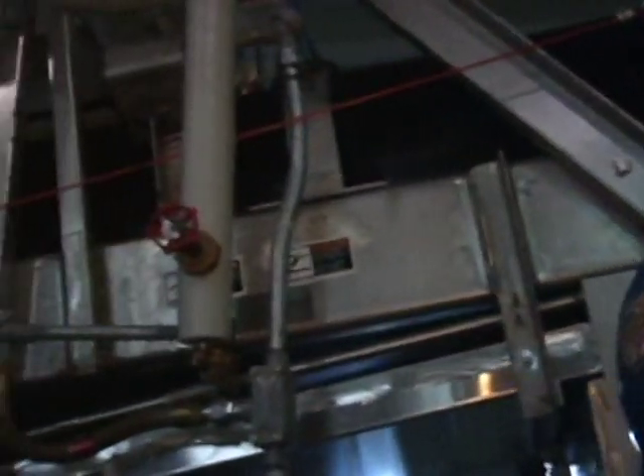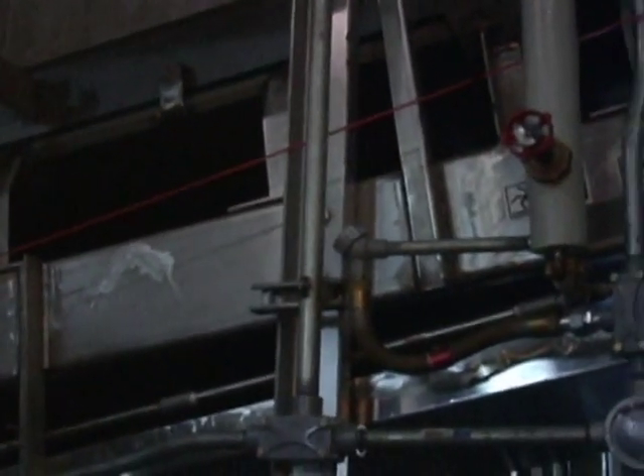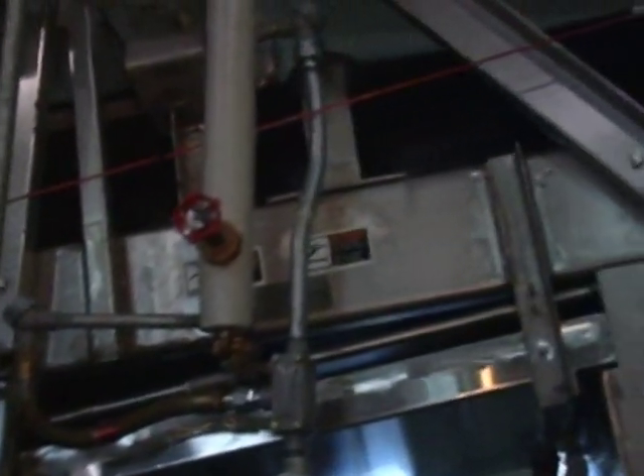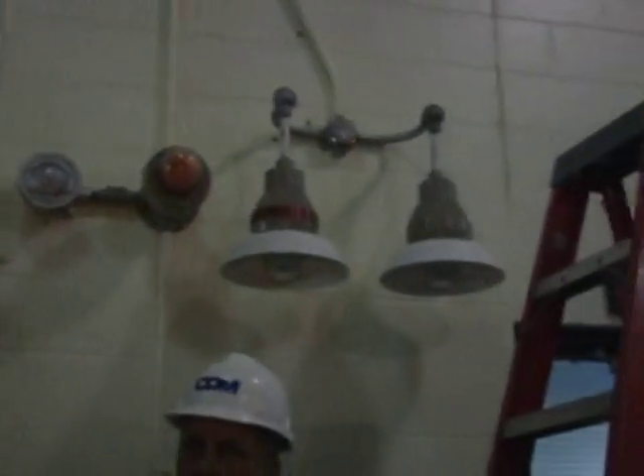The conveyor belt itself is operated from this end of the room. You've got a hand-off-auto switch for the operation of the conveyor. You've got an emergency stop switch here. There's also an emergency stop switch which is tied to the orange cable that runs around the outside of the conveyor itself. Under normal conditions, the way the programming is set up right now, the conveyor will be online. That is interlocked to the equipment downstream, which is the screenings wash press. So the downstream equipment needs to be started first. So when you go to start this equipment up, we're going to start at the roll-off container and work our way back through to the conveyor system itself.